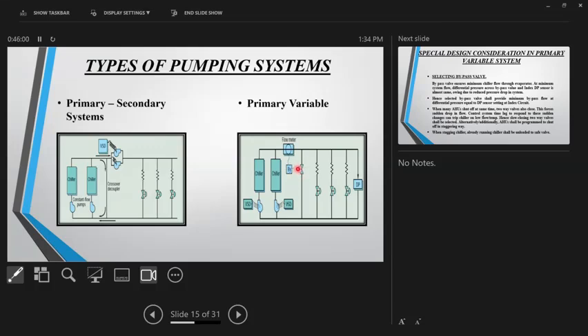If you select this now, all of us know that this valve ensures the health of the chillers, correct? Because the chillers have a minimum flow requirement. You can't reduce the flow of a chiller to, let's say, 10%. There will be some minimum value, 40, 50, 60%, that has to be maintained through the chiller. That duty is done by this valve. So this is a very critical valve which ensures the safety of the system.